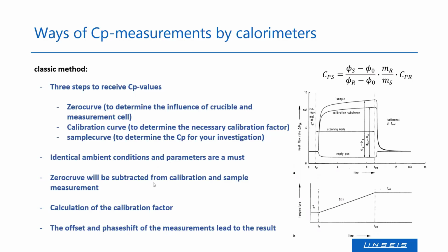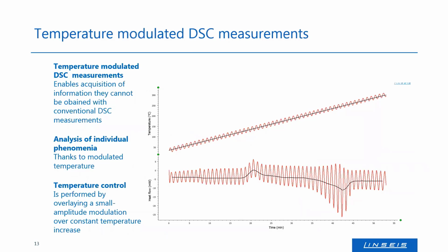So that's it for the classic method, but let's talk about the temperature modulation way. Here we enable the acquisition of some additional information in comparison to the conventional DSC measurement. We don't heat up in a straight way anymore, but we have a sine on our measurement. So we have small amplitudes over our main temperature rise. You can see the conventional measurement in a black line at the upper part of this diagram, and the red one is the temperature modulated way.